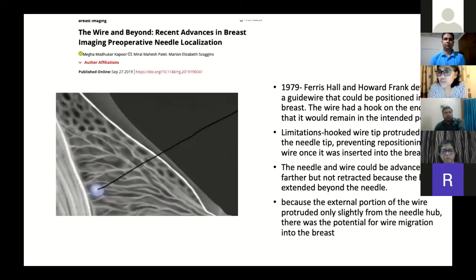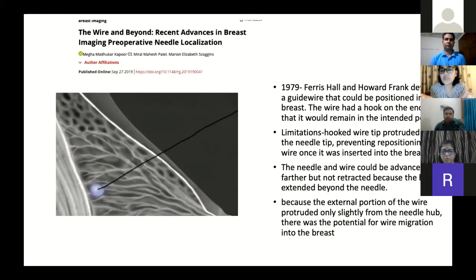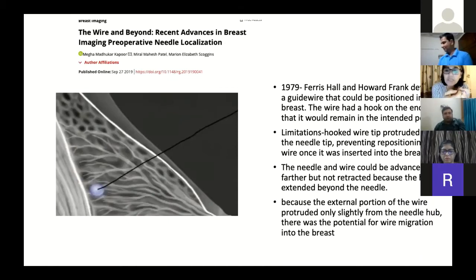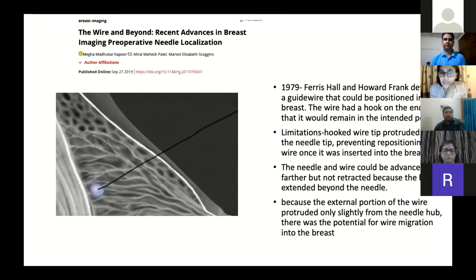In 1979, Ferris Hall and Howard Frank developed a guide wire system that could be positioned in the breast. The wire had a hook on one end so that it would remain in the intended position. The limitation was that it was a single-unit system — the wire came within the needle and the tip always protruded from outside the needle tip. The needle and wire could be advanced further but could not be retracted, because the hook extended beyond the needle and would engage in the tissue. There was also always potential for wire migration into the breast.